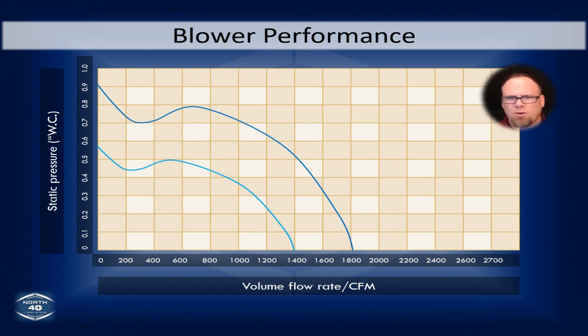The farthest you can go over to the right, let's just say it's the 2200. Okay, you go over to that 2200, that's the fastest this thing is ever going to run. That's taking the blower out of the furnace altogether and setting it out on the floor. It's equally as bad for the motor. It's going to burn itself out because it's freewheeling, but you get my point.